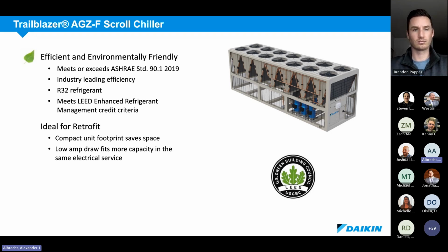So we saw great improvements in reducing footprint, as well as substantial improvements in efficiency, roughly 7 to 15% improvement on IPLV, as well as lower refrigerant charge. R32 has substantial advantages to the market, also in the way of maintenance and serviceability. As a single composite refrigerant, it's able to be charged, reclaimed, reused, both in gas and liquid state. And so the maintenance and serviceability cost is substantially lowered, as well as the cost to the end user.